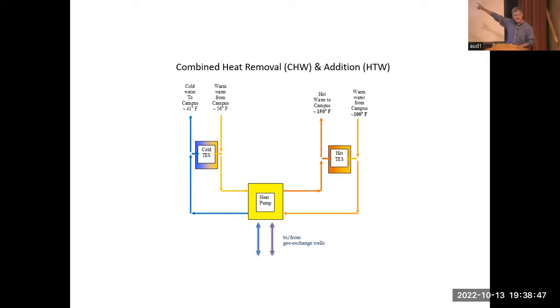Previously we were sending steam at maybe 250 degrees Fahrenheit. Now we're going to send hot water at 150 degrees Fahrenheit. So we need to modify the heating systems in the buildings so they're still adequately heated—we might have to change the radiators, or change the equipment inside the mechanical room that circulates air through the space.